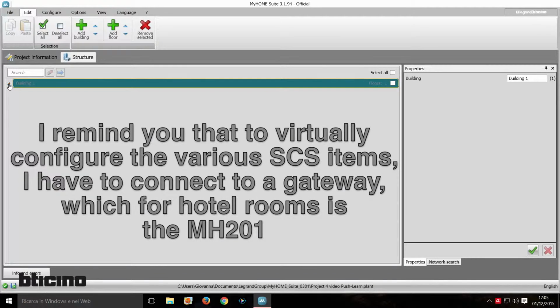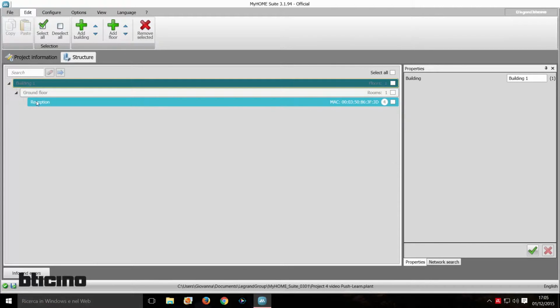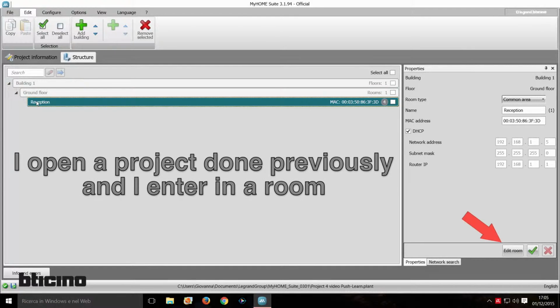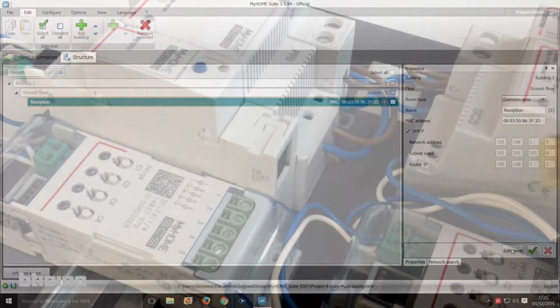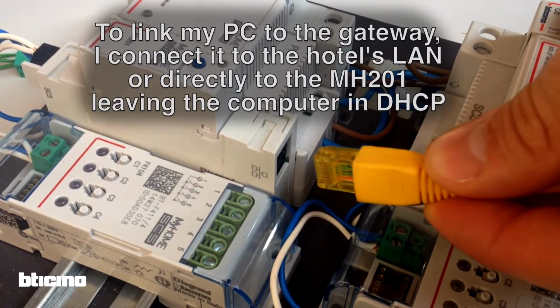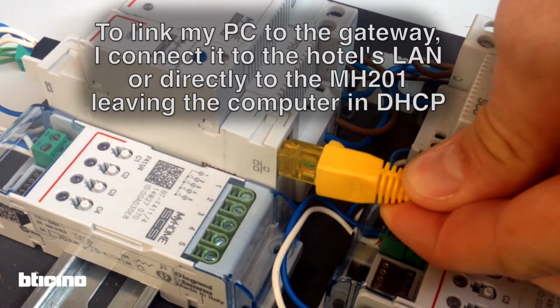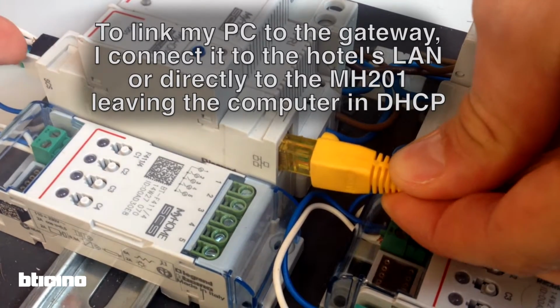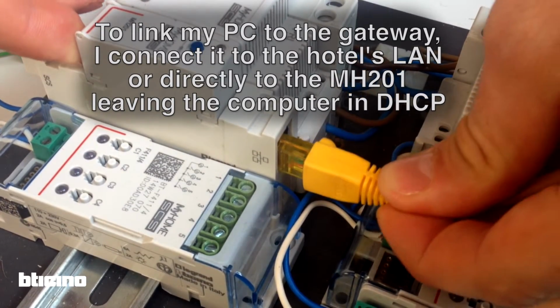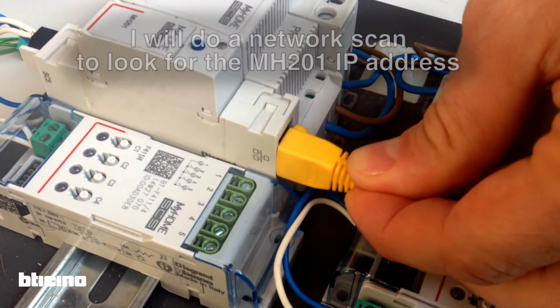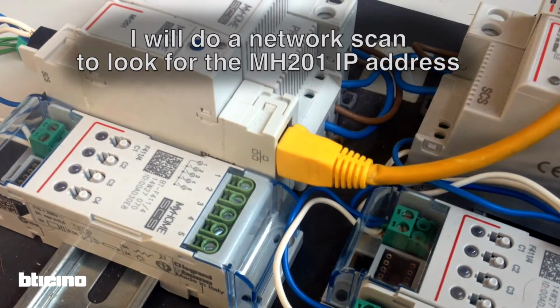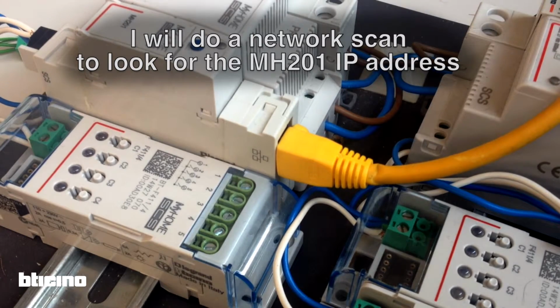I remind you that to virtually configure the various SCS items, I have to connect to a gateway, which for the hotel rooms is the MH201. I open a project done previously and I enter a room. To link my PC to the gateway, I connect it to the hotel's LAN or directly to the MH201, leaving the computer in DHCP. I will do a network scan to look for the MH201 IP address.